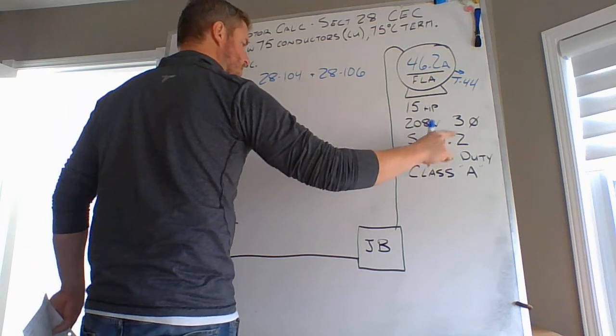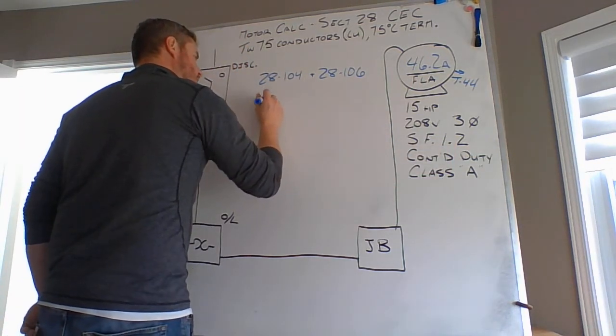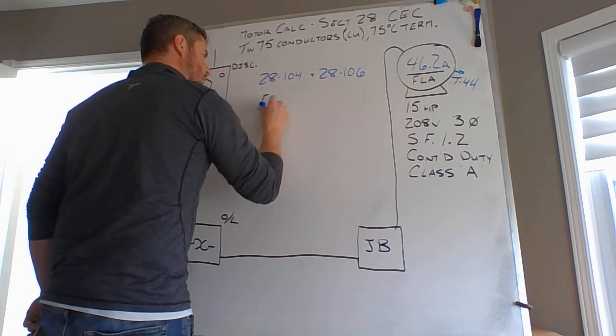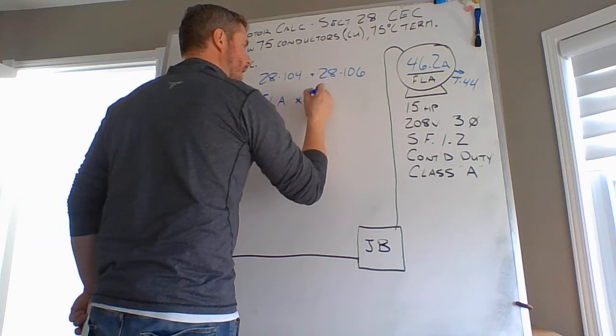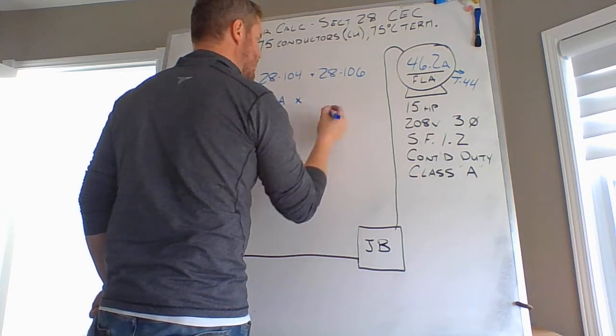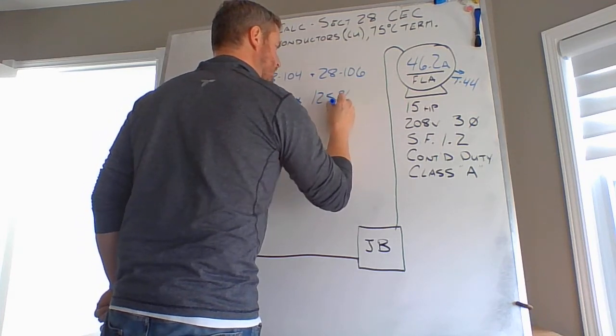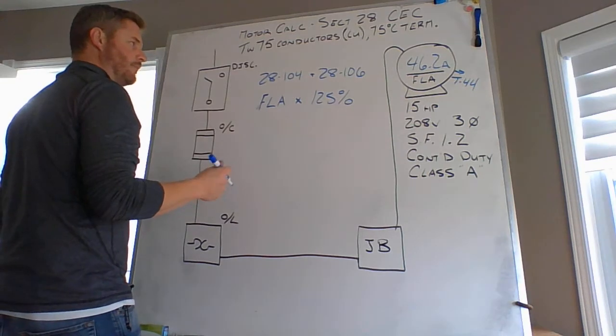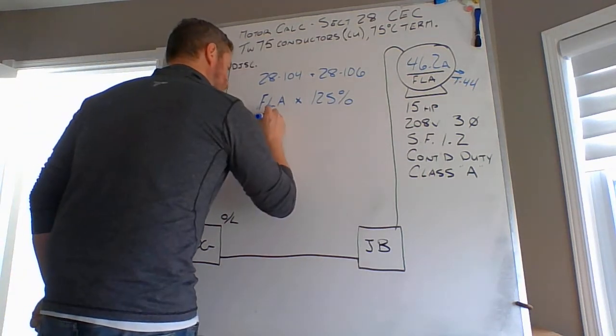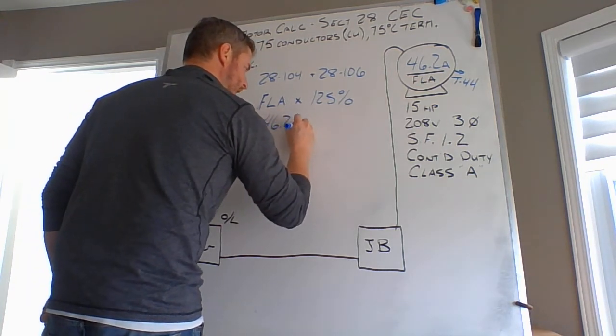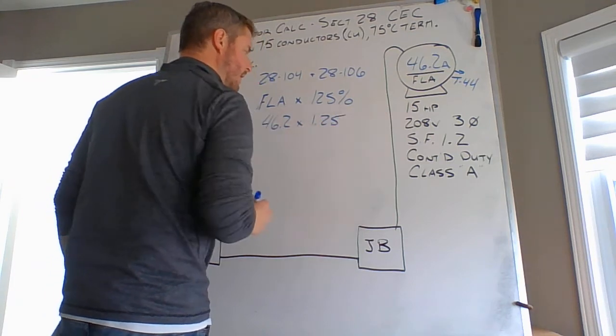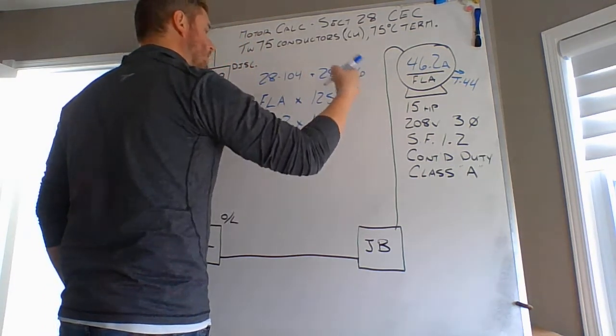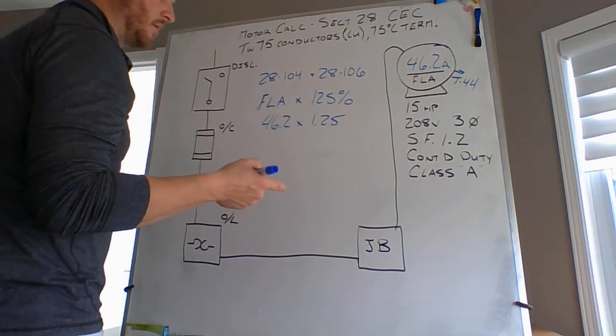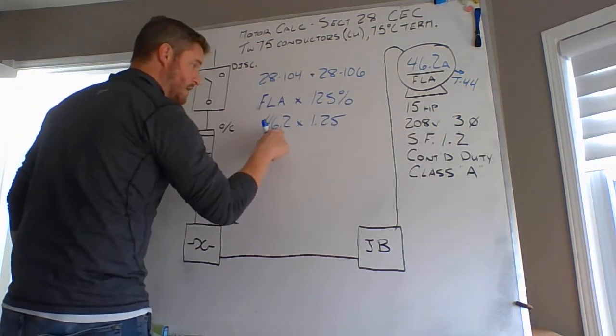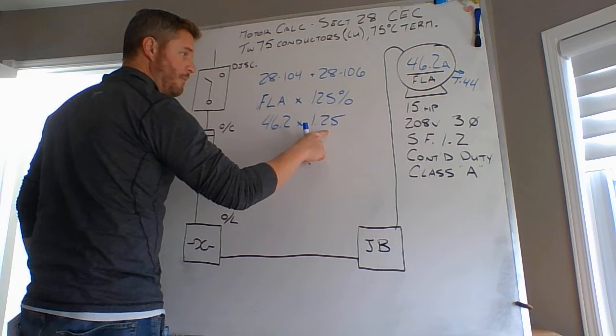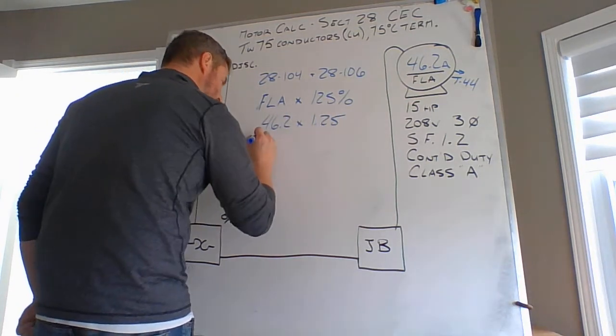Since it's a continuous duty service motor, I'm going to be observing my full load current rating multiplied by what I see in Section 28-106, being 125% of my full load current rating for my conductors. That would therefore translate to 46.2 times 1.25 to achieve the minimum ampacity of my conductors for this specific application. So I'm 46.2 as an FLA, and I'm 125% of the FLA to size the minimum ampacity of my conductor.